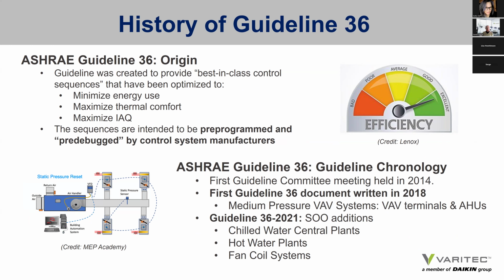The sequences are intended to be pre-programmed and pre-debugged by control system manufacturers so their controllers can adopt the sequences more readily and effectively, and to create perhaps less of a divide between the various controls manufacturers and their controlled solutions for buildings. The original guideline committee meeting occurred in 2014, and the first guideline was written and published in 2018, focusing on medium pressure VAV systems, VAV terminal units, and air handlers. Guideline 36-2021 offers language for chilled water central plants, hot water plants, and fan coil systems. And this guideline will be advancing in the future towards 100% outside air systems, active and passive chilled beams, passive radiant cooling and heating systems, and pressurized laboratories.